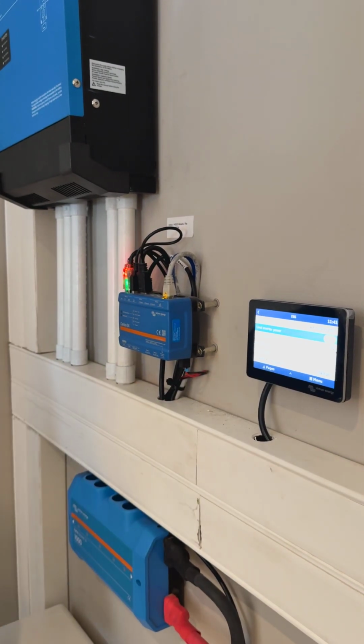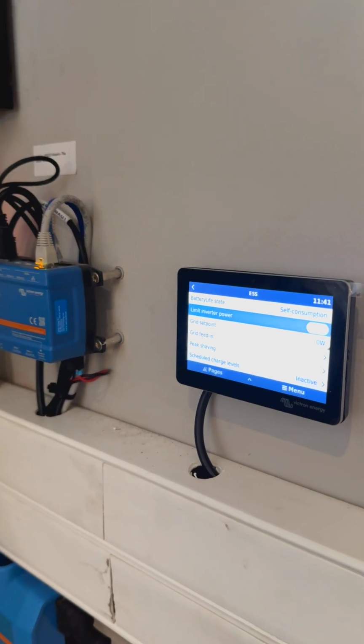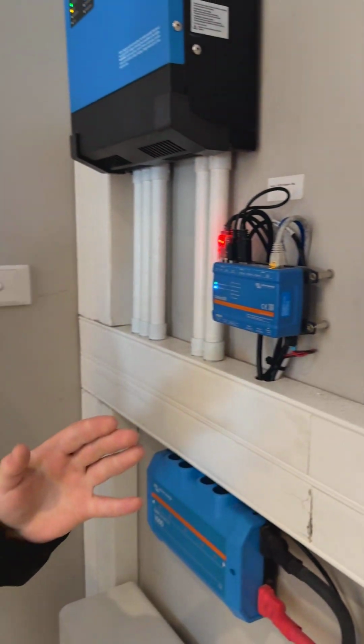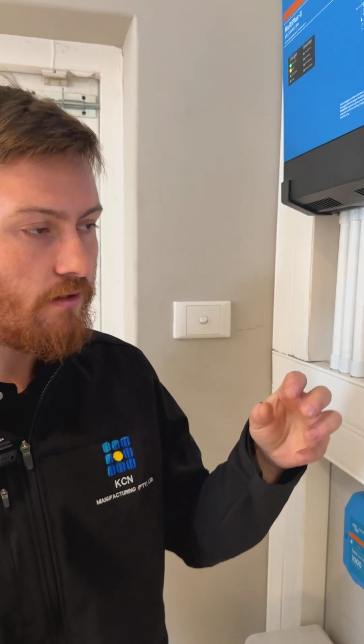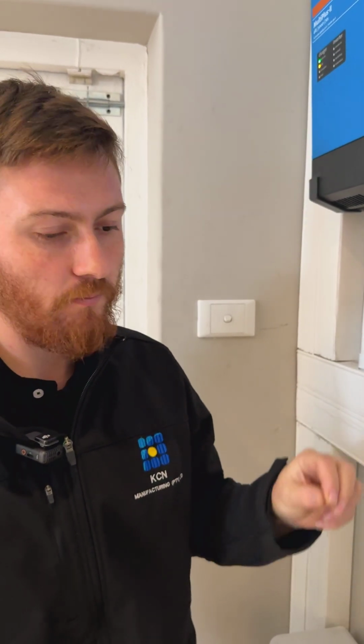Your grid set point, we've discussed this when we did the energy meter videos. This is basically just where you want your grid reference to be. So it will try and keep running the ESS, it will try and keep your grid's load as close to 0 as possible. Please note it will never be on 0 and won't stay on 0. Power does not sit still and wait for better days. Power will always keep on moving, so you'll see it will go to 5 watts, 15 watts, 20 watts, then it drops down to 0, sometimes a -5 for a few seconds, and then it jumps around. So it will happen, that is normal, that is how it's supposed to be.